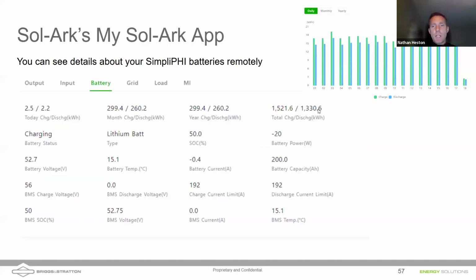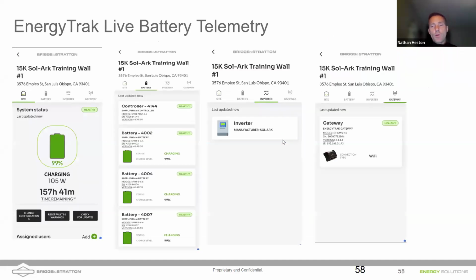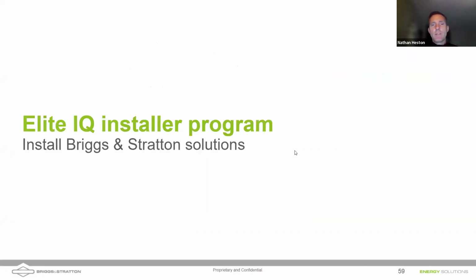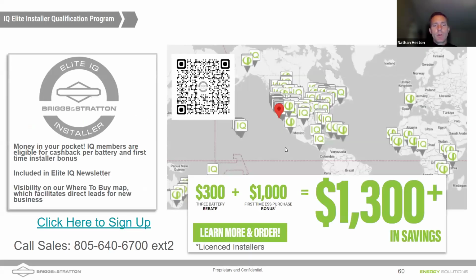You can also see with our communicating batteries a lot of information being pulled in through the Sol-Ark. So you can see the BMS temperature, the battery cell temperature, voltage, state of health. All of these things are monitored inside that Sol-Ark app. If you're looking for more detailed level monitoring, maybe you have a system that's going to include 24 different SimpliPHI batteries, and you want to know how every battery is doing. Well, then the EnergyTrak Gateway that Briggs & Stratton produces gives you a nice opportunity to see detailed battery information on each one of the modules connected. And so we sell that gateway, and you can ask about that to our sales team if you're interested.